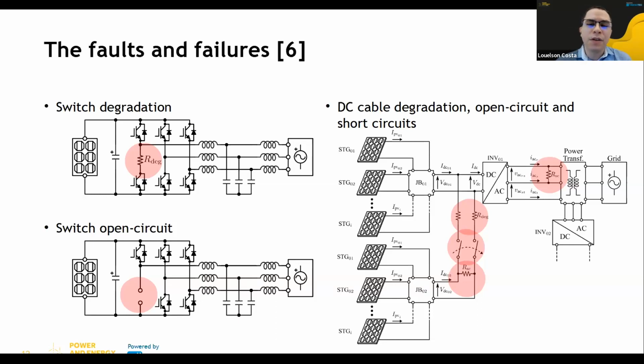Focusing on the inverter or around the inverter, we came up with some faults to implement in our digital twin: switch degradation and switch open circuit. Those are very common faults because the inverter is one of the pieces of equipment with the most failures in a PV power plant - compared to PV modules and transformers, the inverter is much more susceptible to failures.